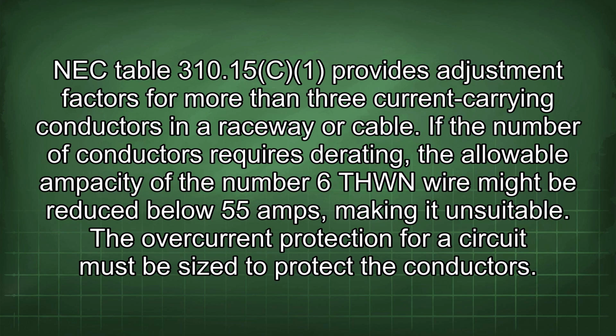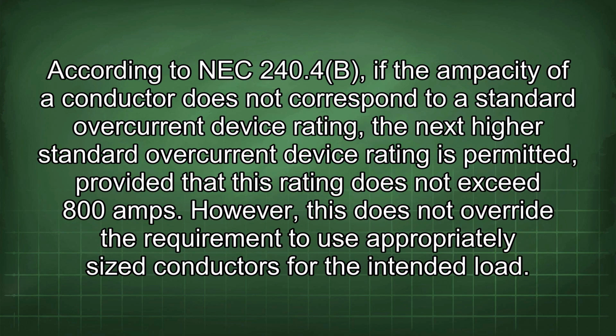The overcurrent protection for a circuit must be sized to protect the conductors. According to NEC 240.4(B), if the ampacity of a conductor does not correspond to a standard overcurrent device rating, the next highest standard overcurrent device rating is permitted, provided that this rating does not exceed 800 amps. However, this does not override the requirement to use appropriately sized conductors for the intended load.